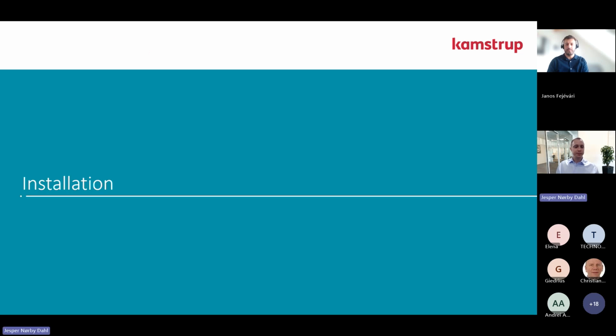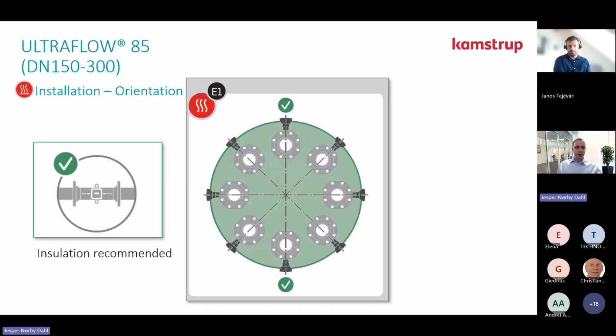Now we come to the installation, because here are also some new things I'd like to show you. Our recommendation is of course to insulate the flow sensor. This helps the performance of the flow sensor, but it's also better because then you don't lose any energy around the flow sensor. And what is new is the direction of the flow sensor. When we are talking about heating, it doesn't matter what direction the flow sensor is installed in. You can have the display pointing down, upwards, to the sides, or at any angle. All these angles are now allowed, and this is quite new.